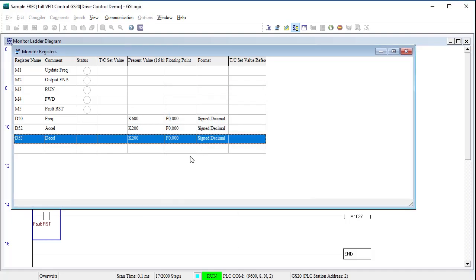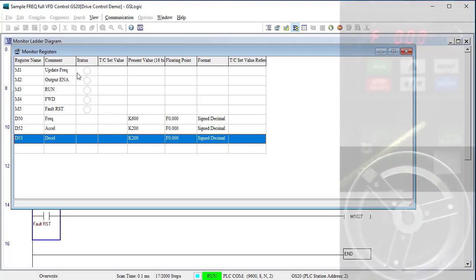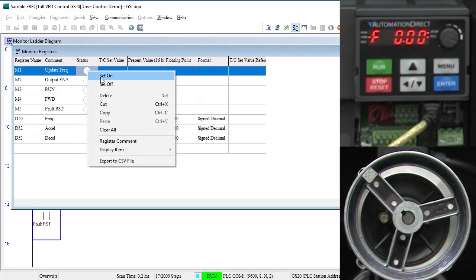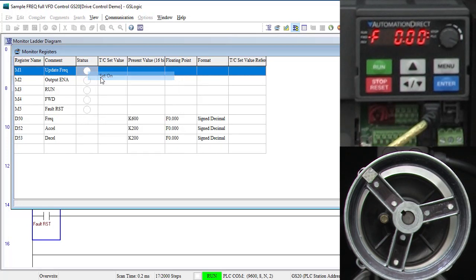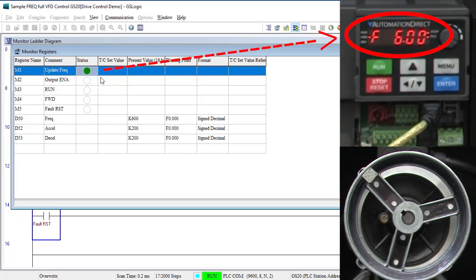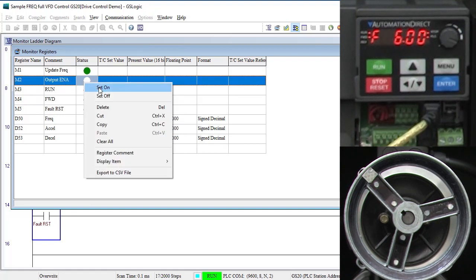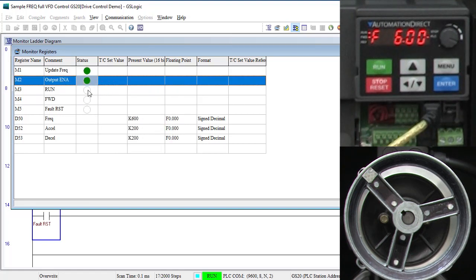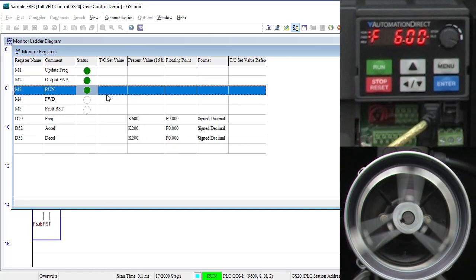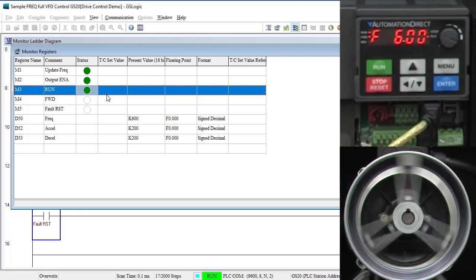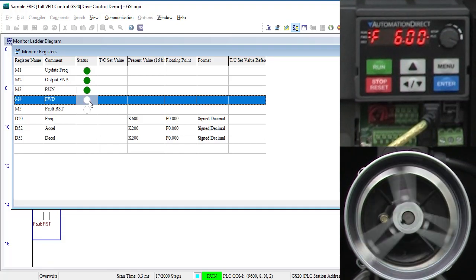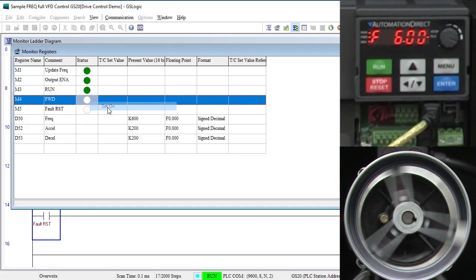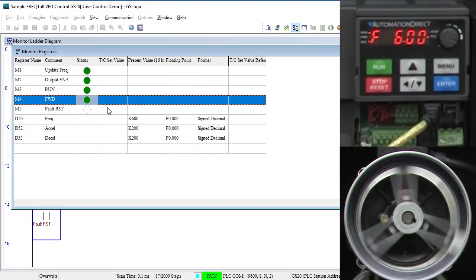Well great, we are all set up and the PLC is running. Let's right click on this to toggle M1 to set the frequency and ramp times we just entered. And we see the drive is now set to 6 Hz. Right click this guy to enable the drive output and right click this guy to switch to run mode. And sure enough, the drive ramps the motor up to speed.